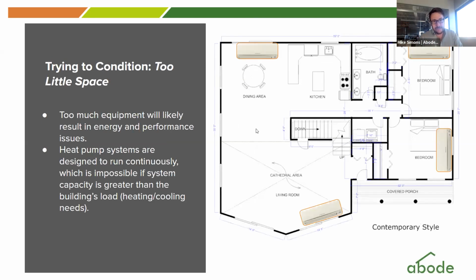Let's look at what happens over here. I said the smallest mini split was 6,000 BTUs. The load here is still 18,000 BTUs. But now we have four mini splits, each requiring 6,000 BTUs. On paper, this is a little bit oversized because it's like 24,000 BTUs worth of heat when only 18,000 BTUs is needed. It's a little oversized, but everything's going to check out.